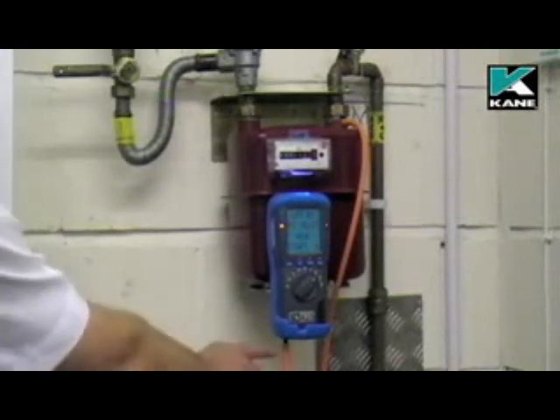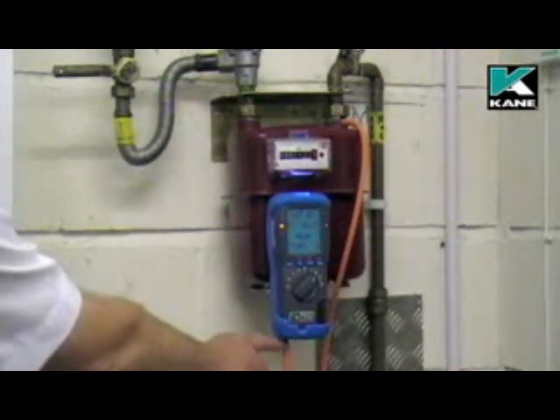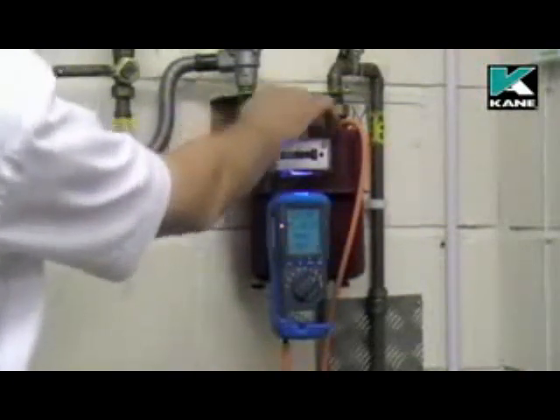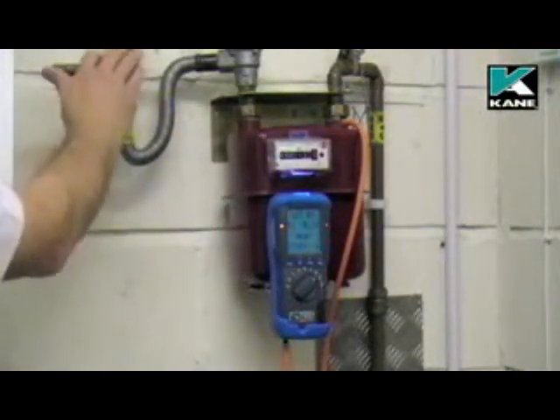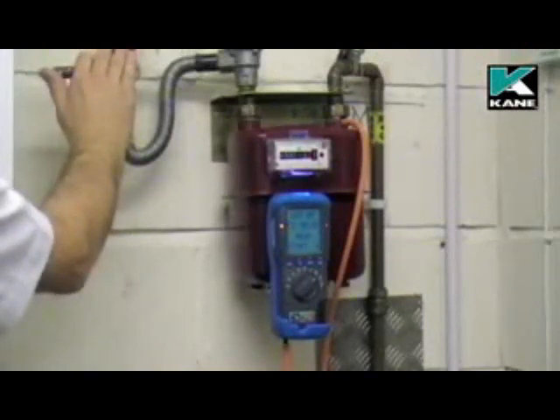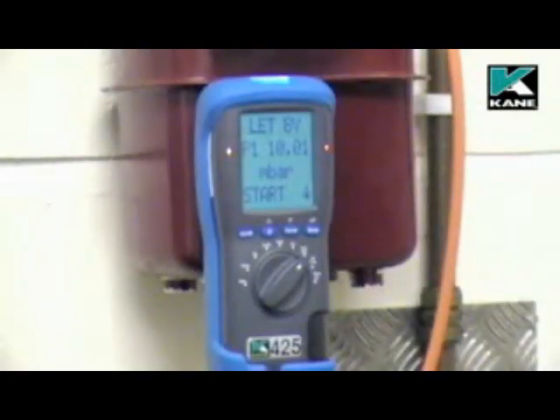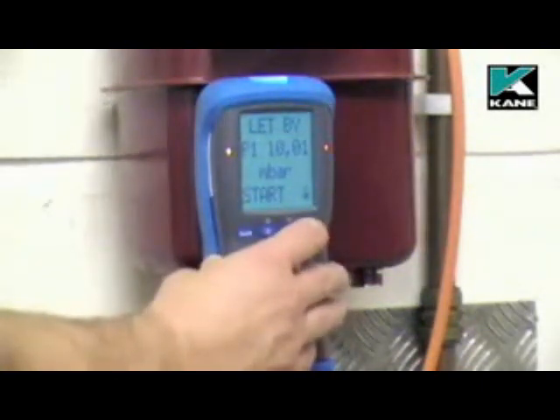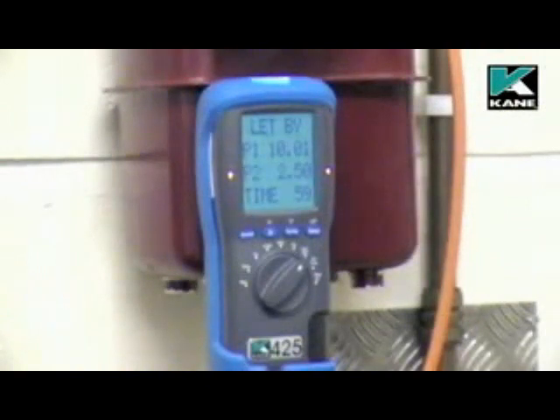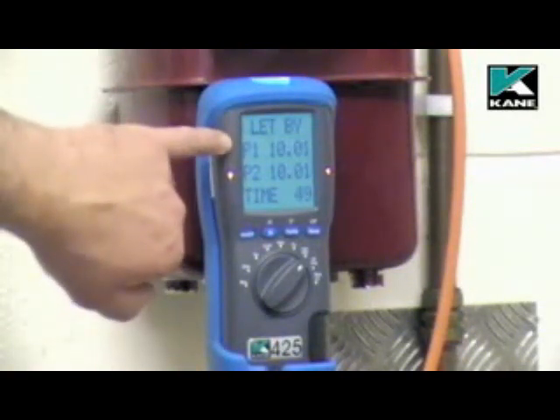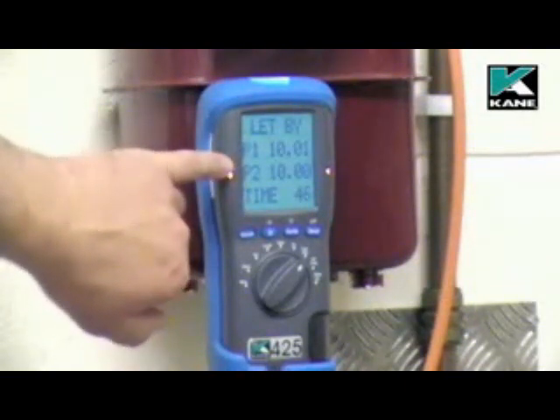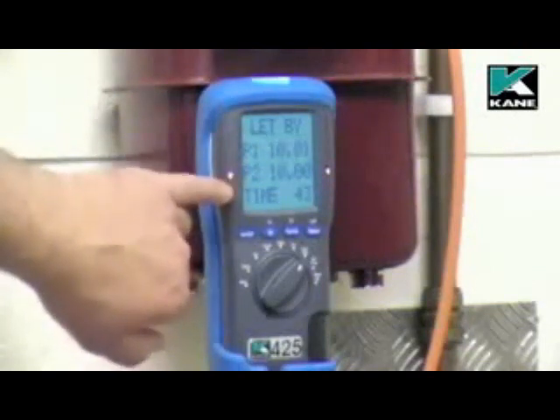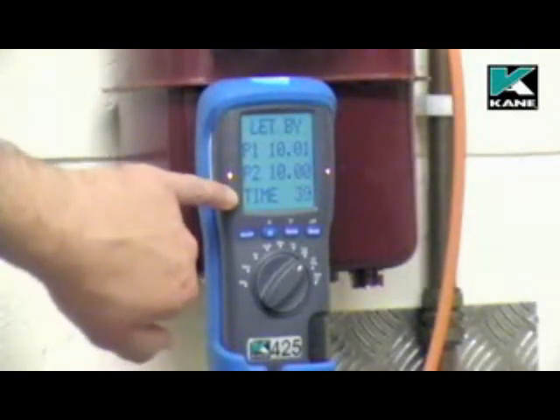I've connected the hose from P1 on the analyzer to the test point on the pressure meter. I'll now increase the pressure to 10 millibars. When the let-by pressure has been set to 10 millibars, press the send button to start the test. P1 is the pressure at the start of the test. P2 is your current pressure, and the instrument automatically times the test for 1 minute.